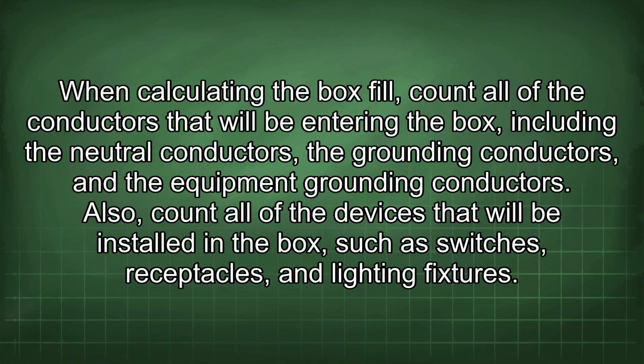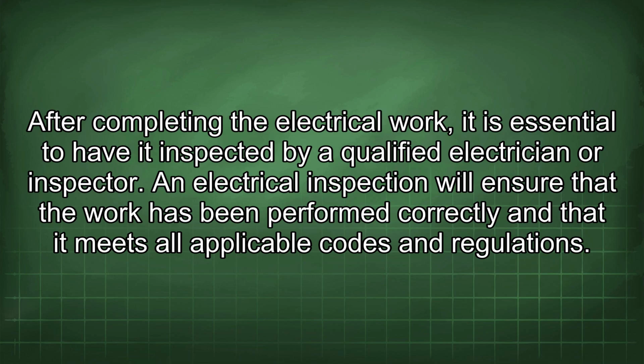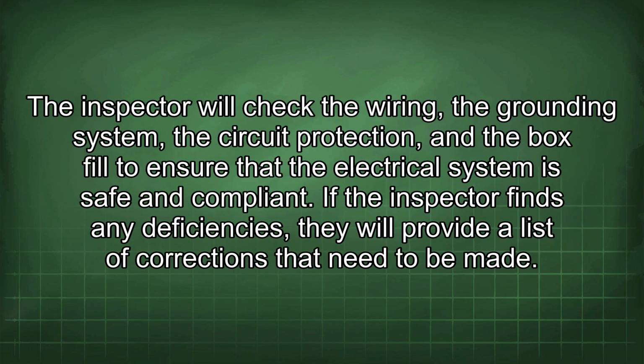When calculating the box fill, count all of the conductors that will be entering the box, including the neutral conductors, the grounding conductors, and the equipment grounding conductors. Also, count all of the devices that will be installed in the box, such as switches, receptacles, and lighting fixtures. After completing the electrical work, it is essential to have it inspected by a qualified electrician or inspector. An electrical inspection will ensure that the work has been performed correctly and that it meets all applicable codes and regulations. The inspector will check the wiring, the grounding system, the circuit protection, and the box fill to ensure that the electrical system is safe and compliant.